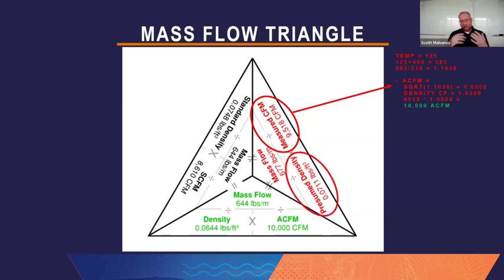Now, to do that, I need to get the right density value. And initially I said, well, you could adjust the presumed density, but no one knows that. No one's measuring that. Or you could just straight up calculate density. And you know what's interesting about this is the only other piece of information I need to know is barometric pressure to get the density value calculated. So if I know the pressure is 28.44, you take that divided by 585, multiply by 1.325, and now I have the air density at the same time I have the volume. And you can see on the triangle below in green, I have the density value of 0.0644, and I have the CFM value of 10,000. And once you have those two values, it's simple math.